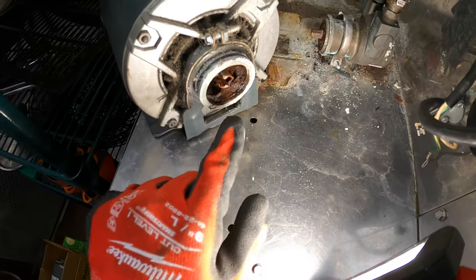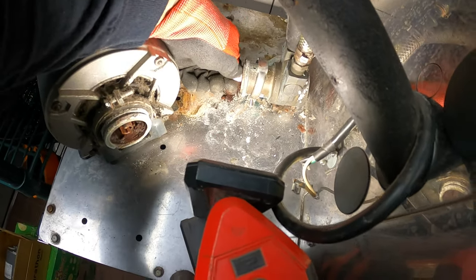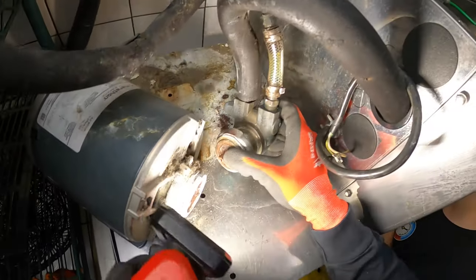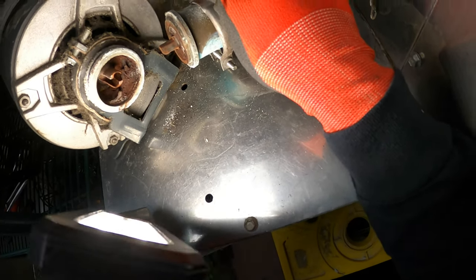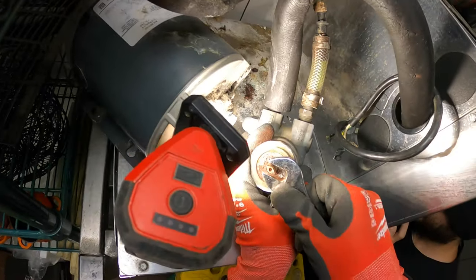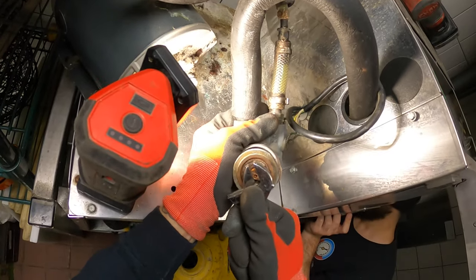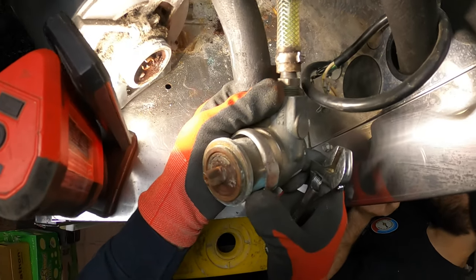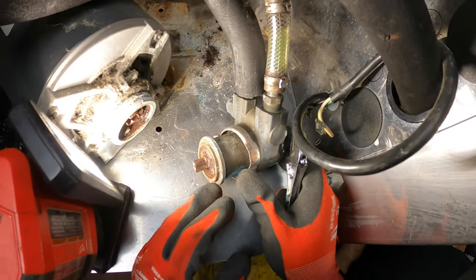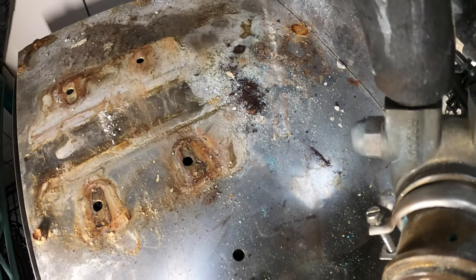This thing is really gunked up in here. I feel like something is wrong here — this pump is that hard to spin. This is the pump, this is the motor. This is really hard to spin. Oh boy, guys, I might need to order this pump. It's ridiculously dirty here.